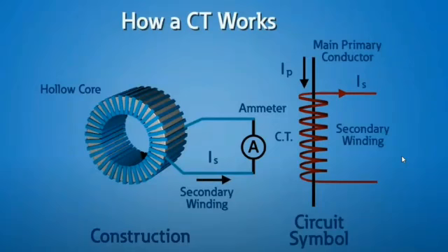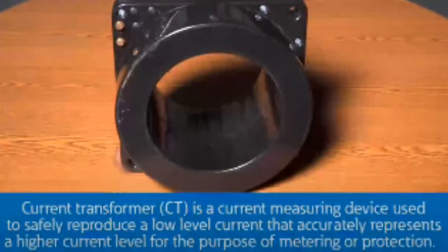If it is left open, then current through the secondary becomes zero. Hence the ampere turns produced by the secondary, which generally oppose the primary ampere turns, become zero. As there is no opposing current, EMF produces high flux in the core, which produces excessive core losses, heating the core beyond the limits. Similarly, heavy EMF will be induced on the primary and secondary side, thus may damage the insulation of the winding.